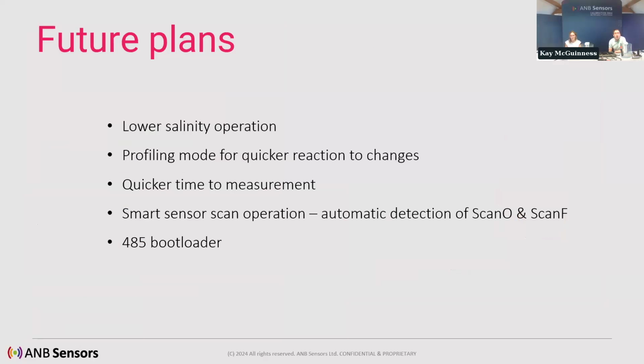Incorporated in that firmware, we have a profiling mode to monitor pH changes quicker than the current firmware. Part of the uniqueness of the sensor and making it calibration free is the reference calibration check, or the reference potential check. We understand that this is a downtime in pH measurement. We understand this could be power consuming, but it means that you don't need to send a field engineer to recalibrate your sensor. We're always looking at ways of speeding this up, and the next release will speed this up quite significantly. We know from customer feedback that Scan O and Scan F isn't always nice to have, because if people are in estuarine environments where the salt solution is changing, they have to flip that manually.